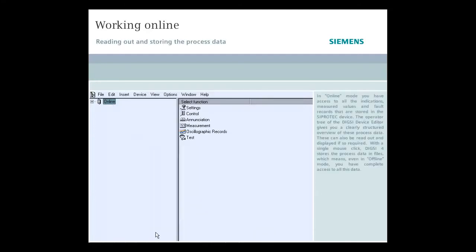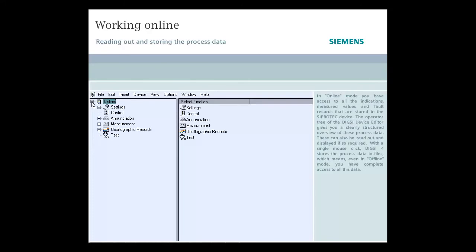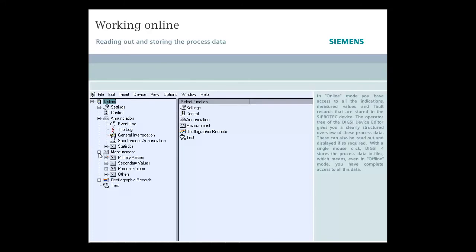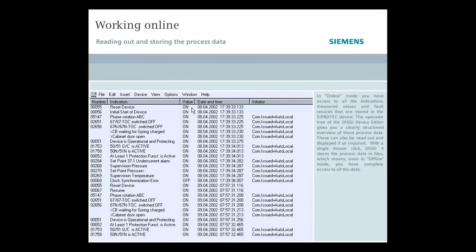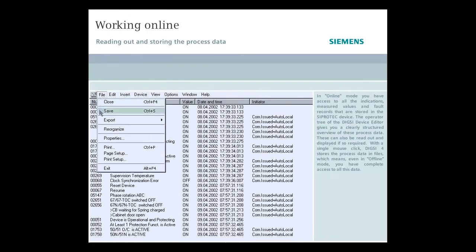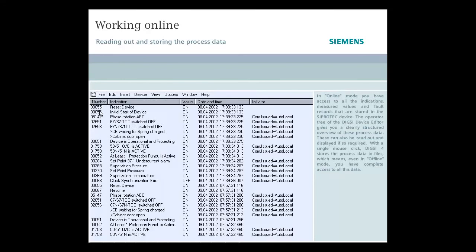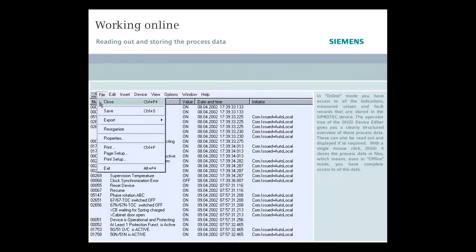In online mode, you have access to all the indications, measured values, and fault records that are stored in the SIPROTEC device. The operator tree of the DIGSI device editor gives you a clearly structured overview of these process data. This can also be read out and displayed if so required. With a single mouse click, DIGSI 4 stores the process data in files, which means, even in offline mode, you have complete access to all these data.